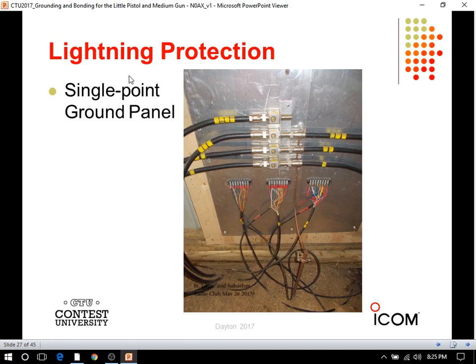If it's still there, it's probably okay. Most polyphasers have removable gas discharge tube cartridges, so after a lightning storm you unscrew it, take it out, and inspect it. If you see burn spots or big pits in the little electrodes inside the glass tube, or if there's nothing left but two wires, then you replace it. You have to open it up and check it out. Some types will tell you if an MOV is compromised, but those are expensive.